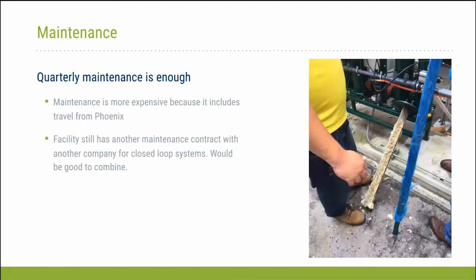Yeah, so in our case, we're finding that quarterly maintenance is really the right thing to do. Initially, neither the vendor nor us knew how frequently we would have to clean. We were kind of making a guesstimate based on how much hardness minerals we had in our makeup water. The initial recommendation from the vendor was that we might have to clean it the first time at 3 months.